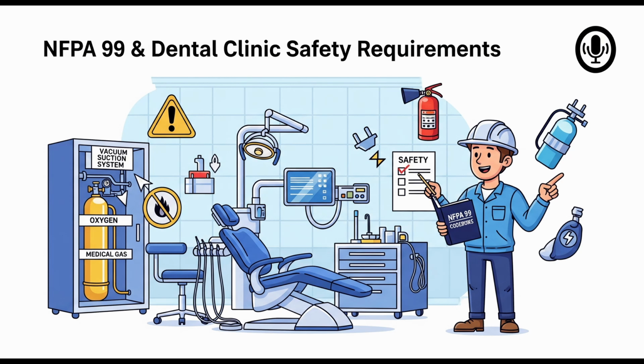And finally, just to reiterate for someone wanting to look this up, what were the key chapters and sections of NFPA 99 2021 we focused on for this dental clinic deep dive? We drew heavily from Section 15.4, Dental Gas and Vacuum Systems, Section 5.3, Category 3 Systems, Chapter 11, Gas Storage, Chapter 6, Electrical Systems, especially Section 6.6 for Emergency Power, and Chapter 5, General Medical Gas Vacuum Requirements like piping and testing. We also touched on Chapter 4, Risk Assessment, Chapter 9, HVAC for ventilation, and Chapter 3 for definitions like single treatment facility. Fantastic.